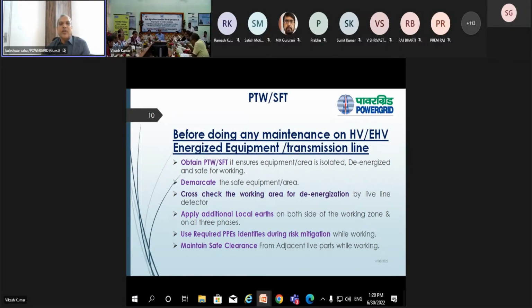So after that, PTW and SFT. Before doing any maintenance on HV, EHV energized equipment or transmission line, first and foremost we have to take the permit to work or sanction for test. And it ensures the equipment area is isolated, de-energized and safe for working.